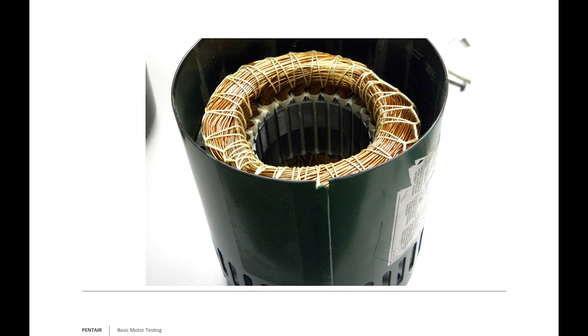Right now I'm talking about above-ground pumps, but I'll also cover submersibles — they share a lot of characteristics and both have windings. The problem with submersibles is they're epoxy-coated and you can't open them up to look. For an above-ground open drip-proof motor, I usually don't measure the windings with a meter first. Instead, I shine a light in there and look: are the windings still that nice copper? Is the overspray complete, not bubbled or blistered? Are all the strings still in place?